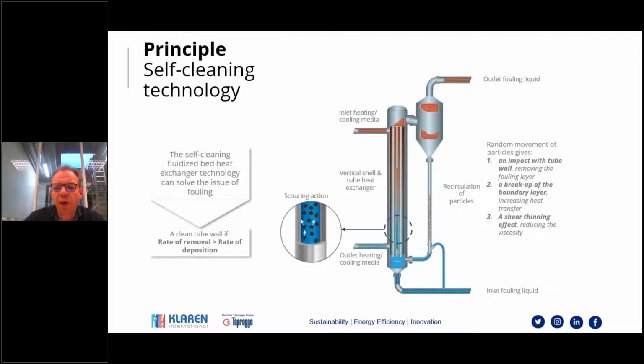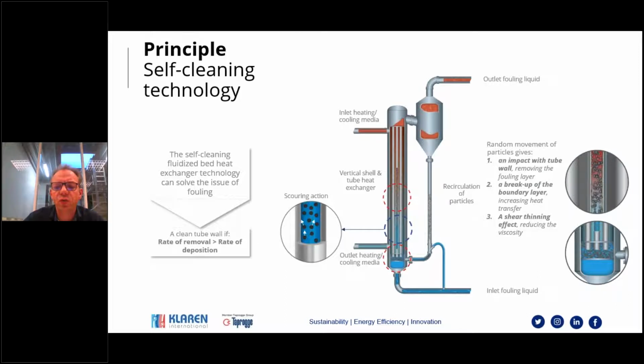Our self-cleaning technology is based on the fluidized bed of cleaning particles at the inside of a vertical shell and tube heat exchanger. And I will start the animation so that you have also a bit of an idea of how it works. What we do is we supply cleaning particles at the inlet of a vertical shell and tube exchanger. And those cleaning particles are fluidized with the upward flow in the inside of the heat exchanger tubes. And on average, those cleaning particles will move upward. So in fact, the tube velocity is somewhat higher than the falling velocity of this swarm of particles. So they will move upward in the tube.